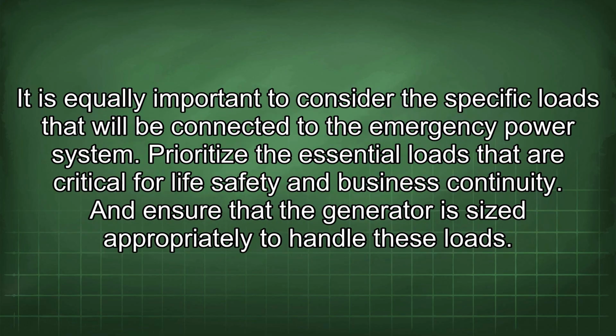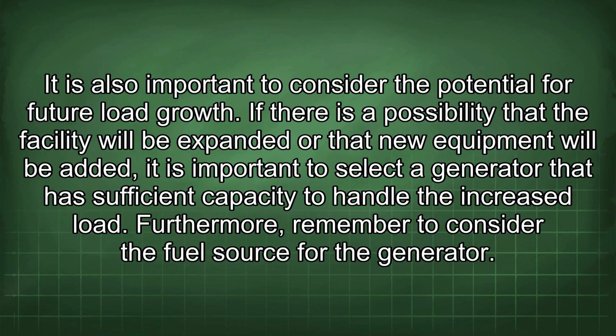It is equally important to consider the specific loads that will be connected to the emergency power system. Prioritize the essential loads that are critical for life safety and business continuity, and ensure that the generator is sized appropriately to handle these loads. It is also important to consider the potential for future load growth. If there is a possibility that the facility will be expanded or that new equipment will be added, it is important to select a generator that has sufficient capacity to handle the increased load.